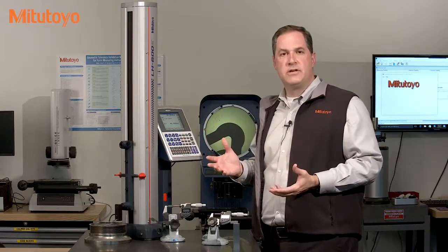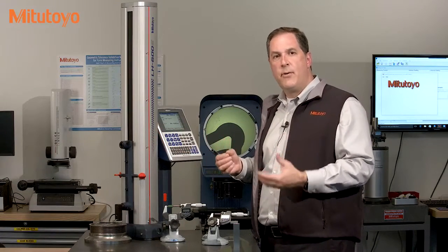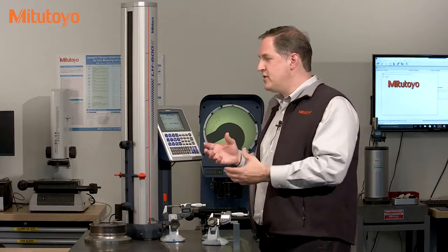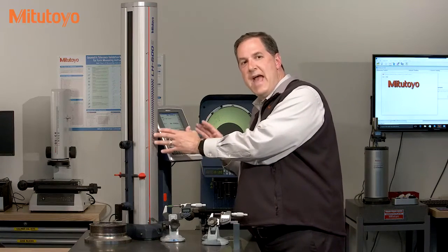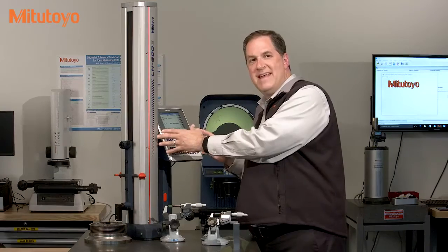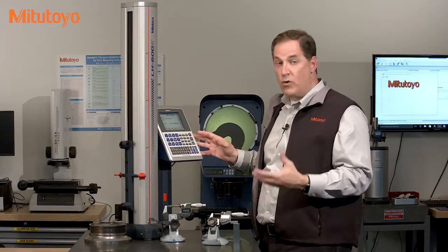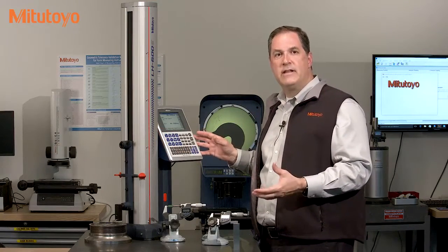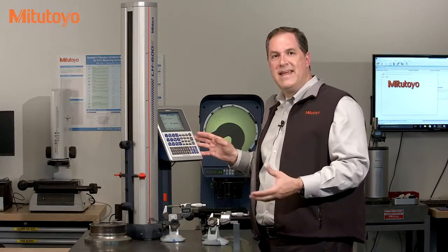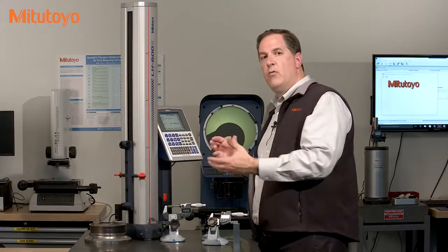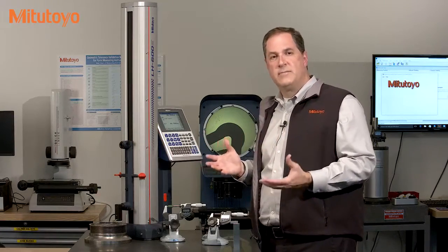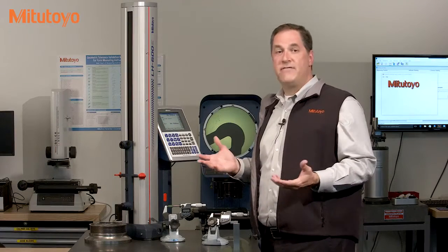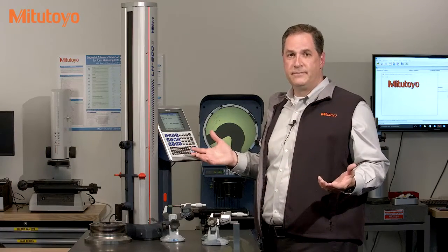And that's where calibration comes in. In this case, the purpose of calibration is to determine the status of the accuracy of this linear height. Is it performing or still performing as accurately as expected? Is the current accuracy within stated requirements and specifications? And if not, what do we do?